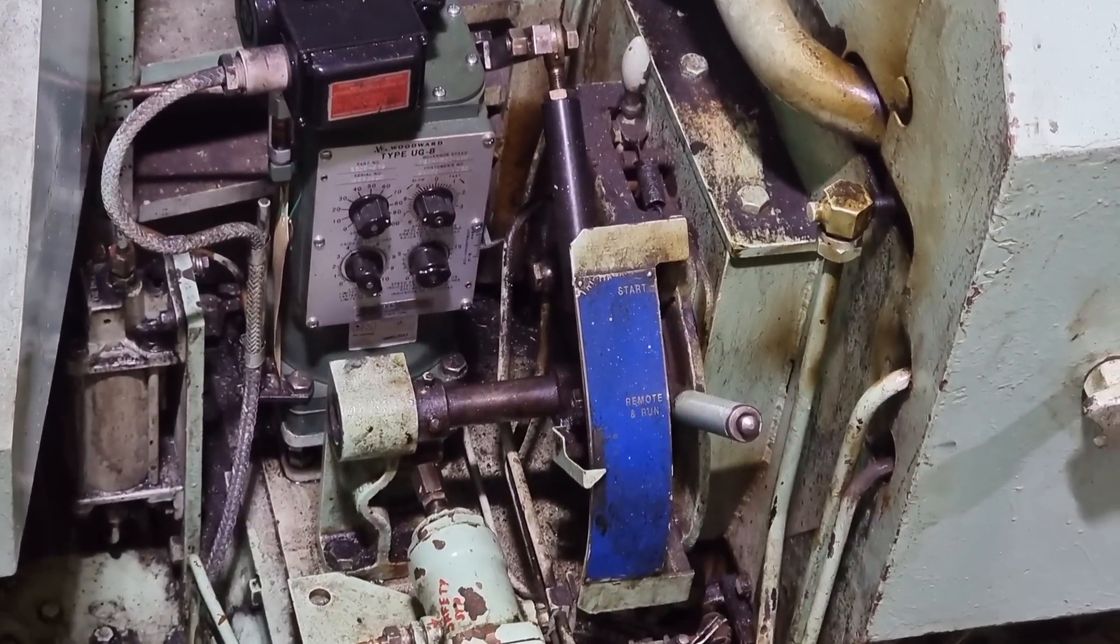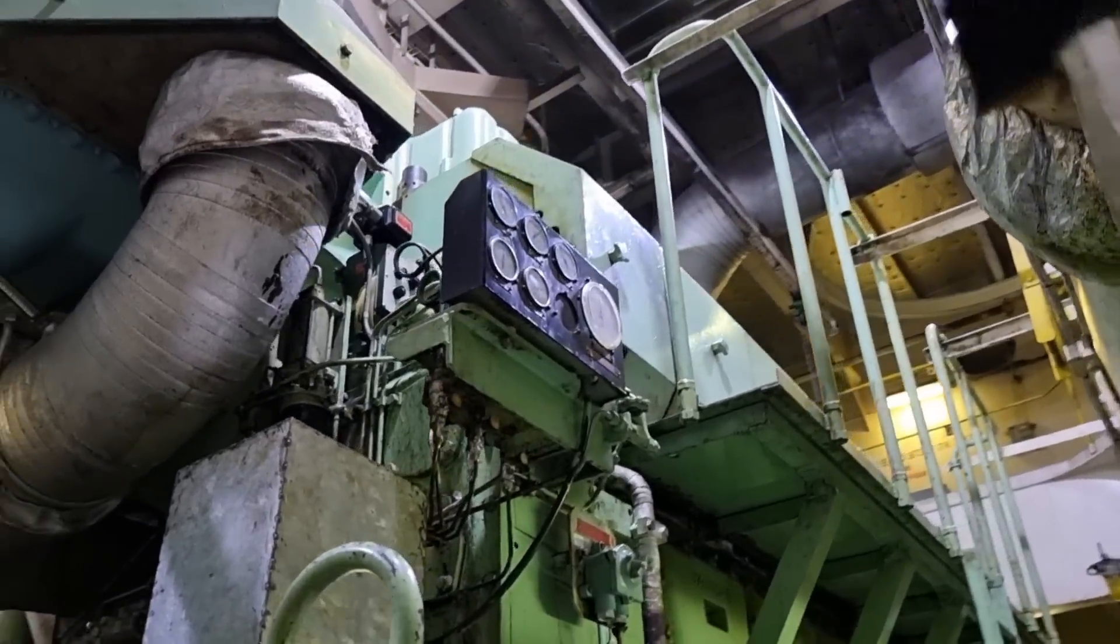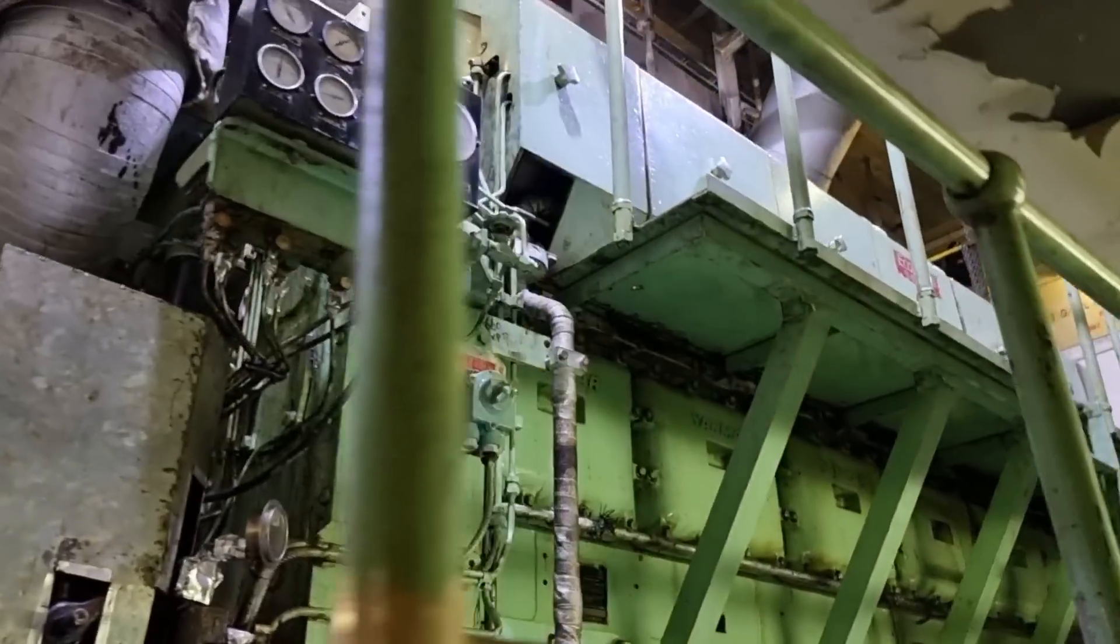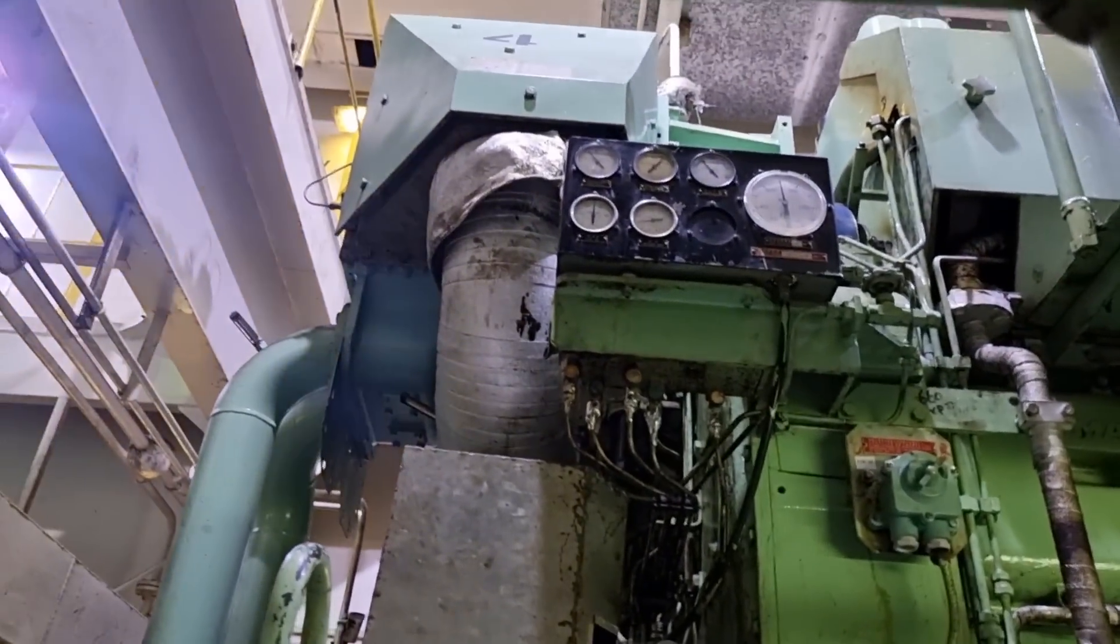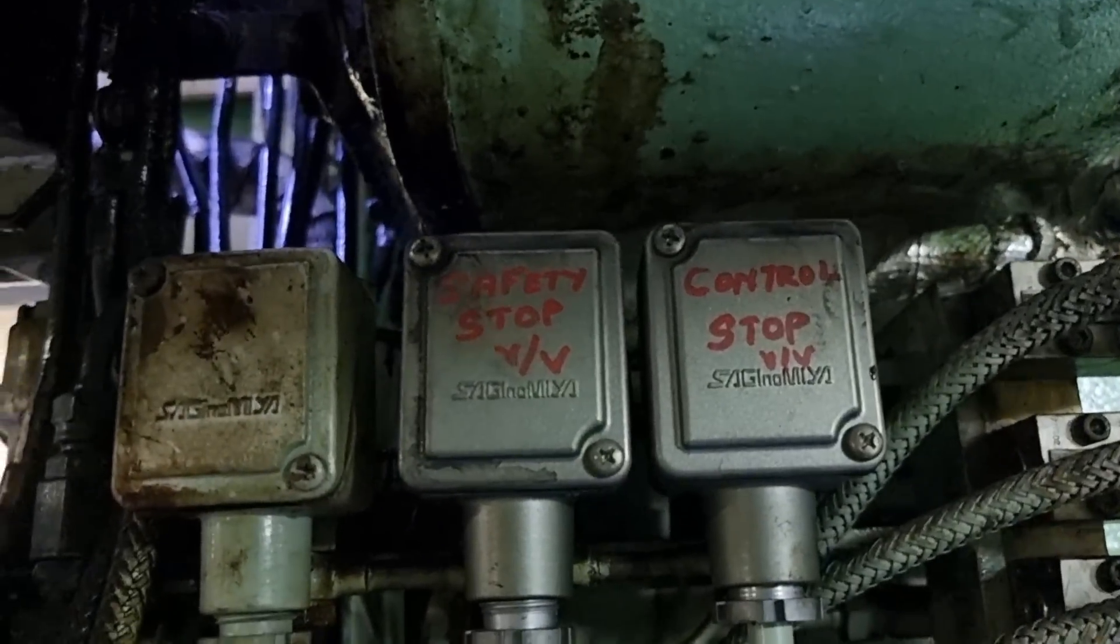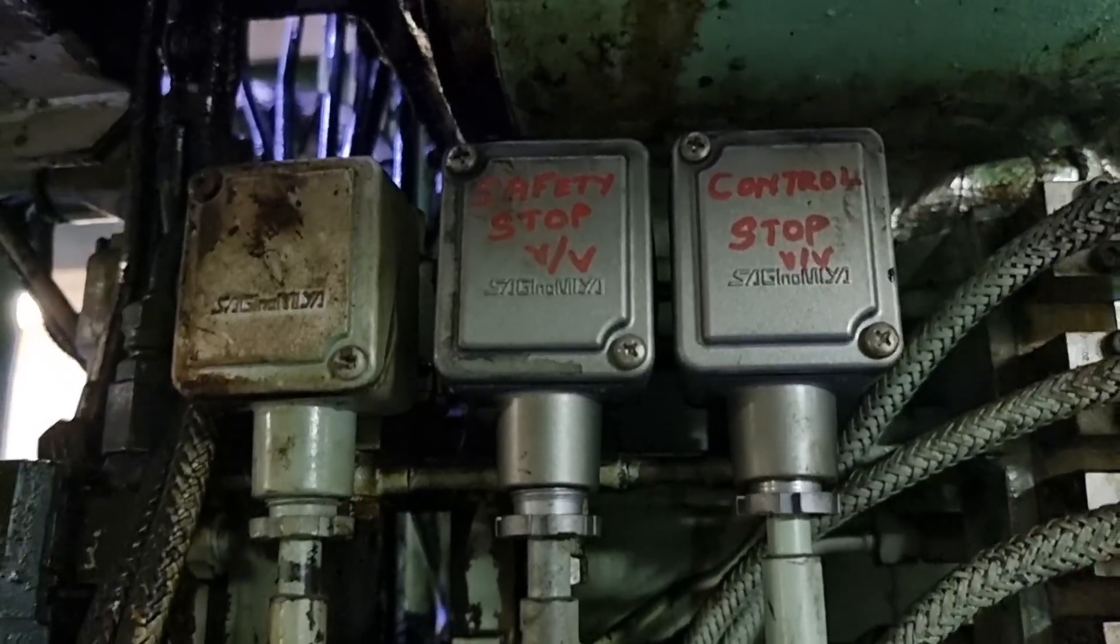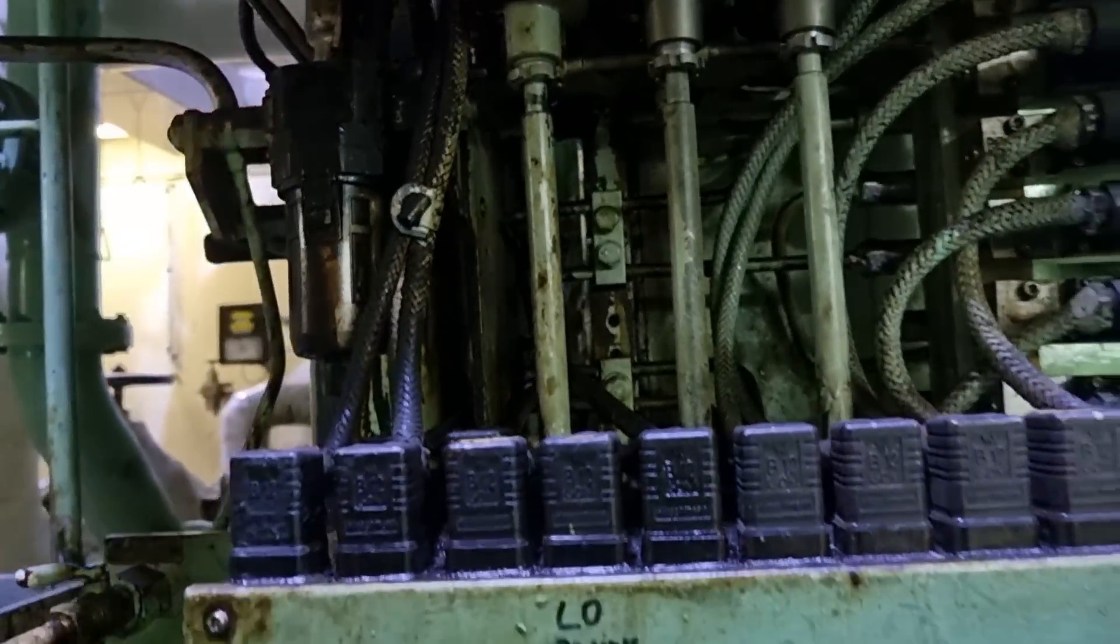By the way, this is the handle for stopping operation. In this particular generator, the stopping operation will require to activate two solenoid coils. And these are the control stop valve and the safety stop valve.